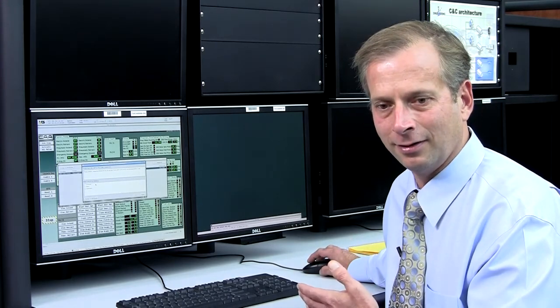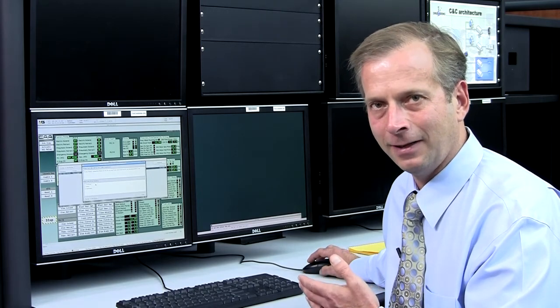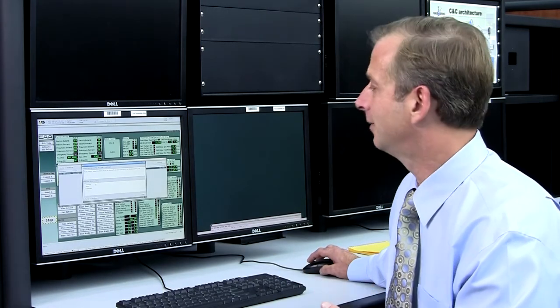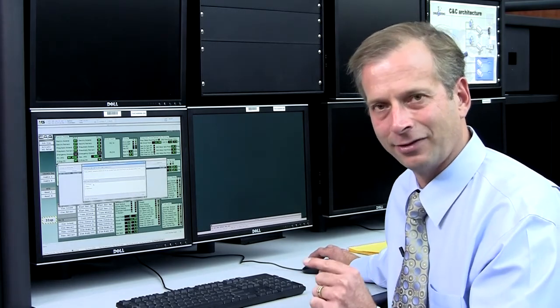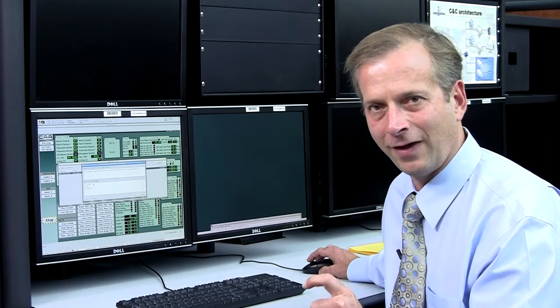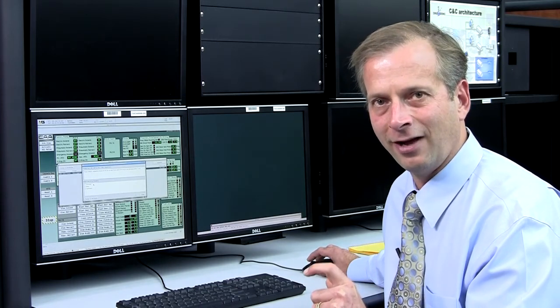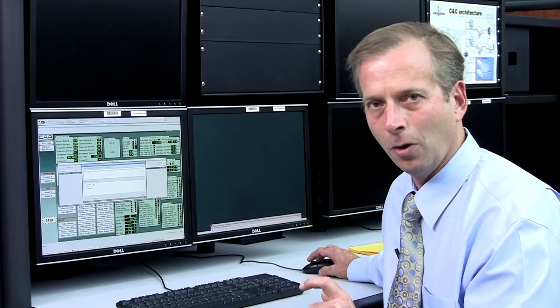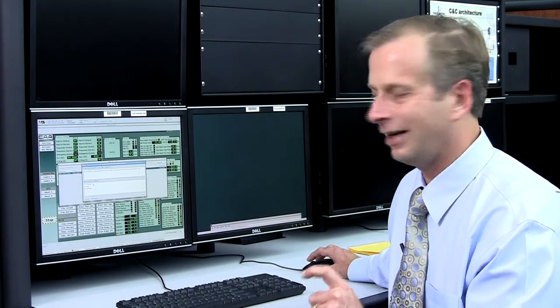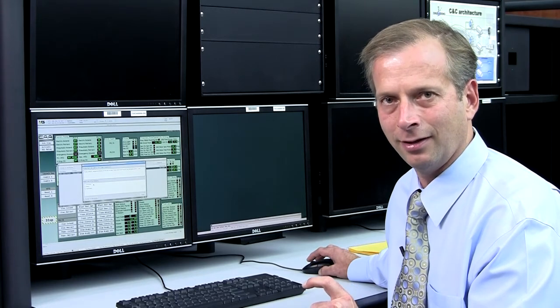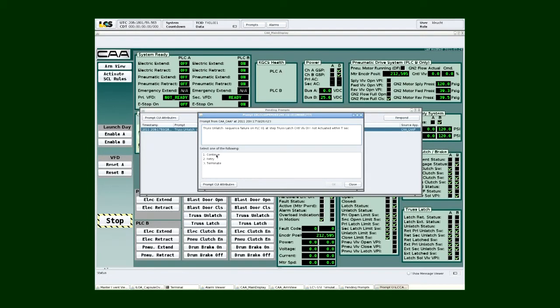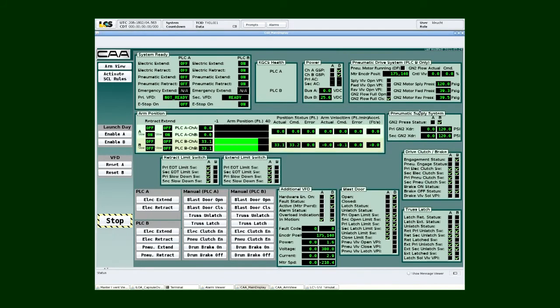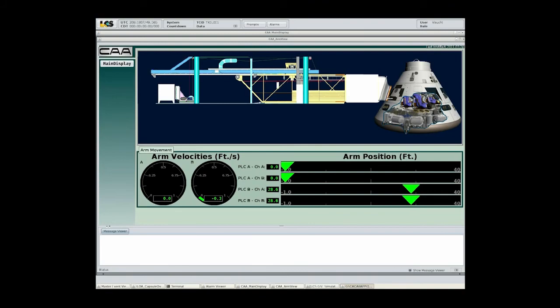Then if I select continue, I'm going to issue a command from here to the PLC to tell it to ignore that particular failure and continue to the next step. In this case, the next step is going to be to check to see if the actual latch pin physically became unlatched. And since I only simulated a failure of the electric switch that indicates the position of the valve, and I did not insert a failure of the physical valve itself, the valve actually did cycle open. The latch pin actually did drop out in the simulator. So when I select continue and tell it to bypass the limit switch error, we expect the system to continue. So I'm going to go ahead and select continue and select OK. And if you notice, my arm continues motion. I'm now retracting. I'm currently at 31.8 feet. And my actual velocity is right around minus 0.2 to minus 0.3 and our target of minus 0.28 feet per second. And our arm will continue operation in the retract position.